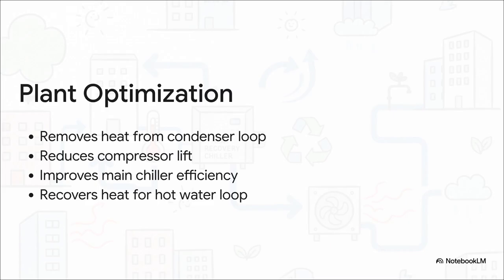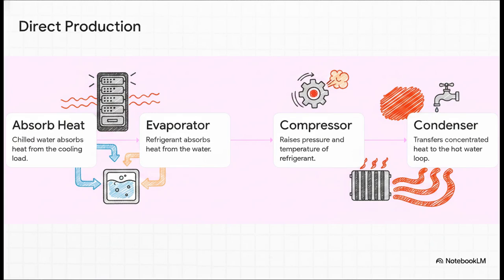By arranging the heat recovery chiller to remove heat from the condenser water loop before that water even reaches the main chillers, you achieve something pretty amazing. You're giving the main chillers cooler condenser water. This reduces their compressor lift, meaning they don't have to work nearly as hard, which vastly improves their efficiency. And the heat that was removed? It's sent straight to the hot water loop instead of the cooling tower. You're taking the burden off the main chillers and the boilers at the exact same time. It's a total win-win. The second application is direct production.